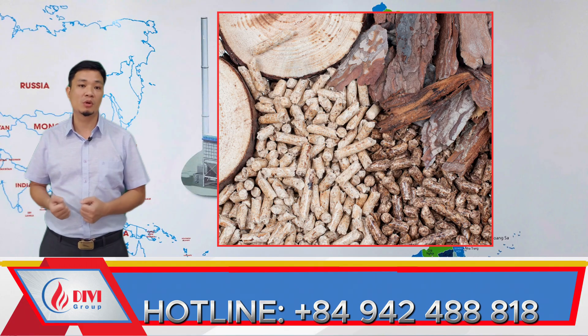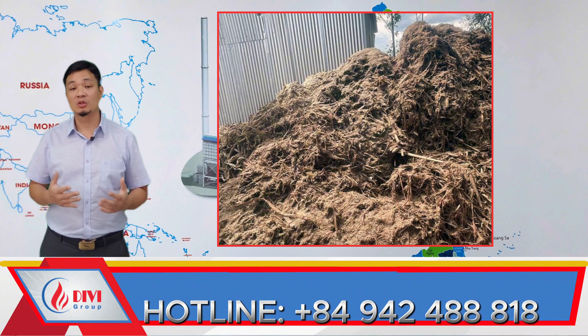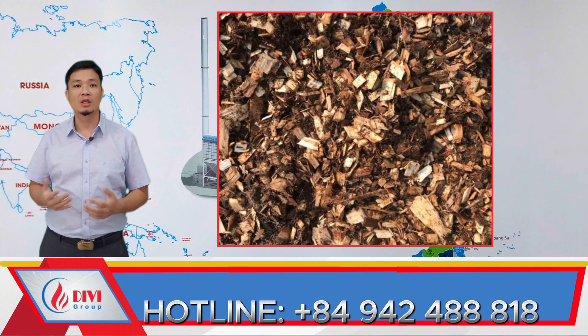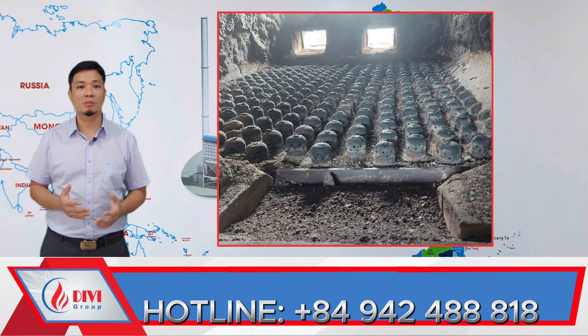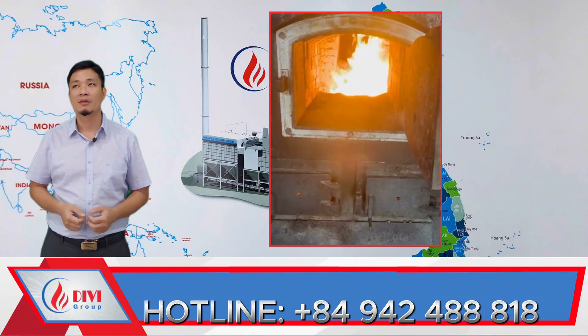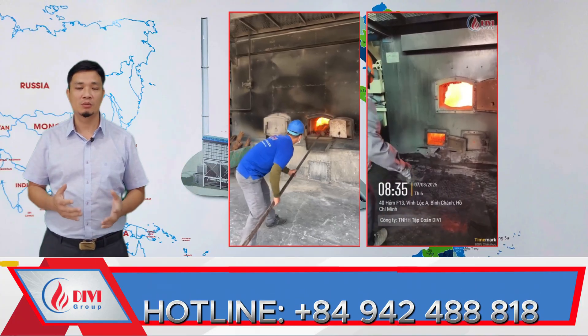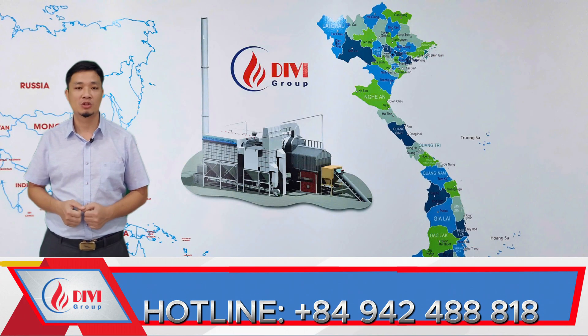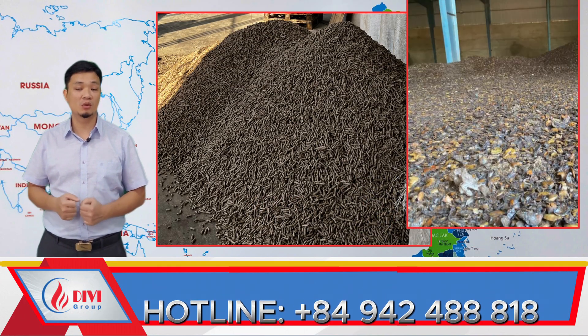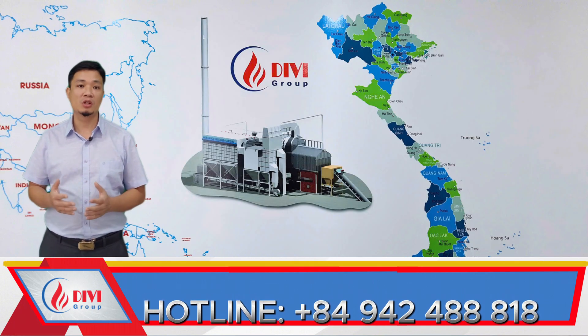Case three: both fans are working properly. Then you must check fuel quality. In some cases, the calorific value of the fuel may be too low due to excessive moisture content, mold or decay, or high levels of impurities like sand, gravel, or rocks. If such impurities clog the air holes on the grate, they reduce oxygen supply and lower combustion efficiency. In this case, you'll need to rake out the debris to restore airflow through the grate. Additionally, if the fuel quality is too poor — such as overly moist biomass, moldy wood, or low-calorific agricultural waste — you should supplement with high-calorific fuels like wood pellets or dry chopped wood. This helps compensate for the lack of thermal energy and allows the boiler pressure to recover faster.